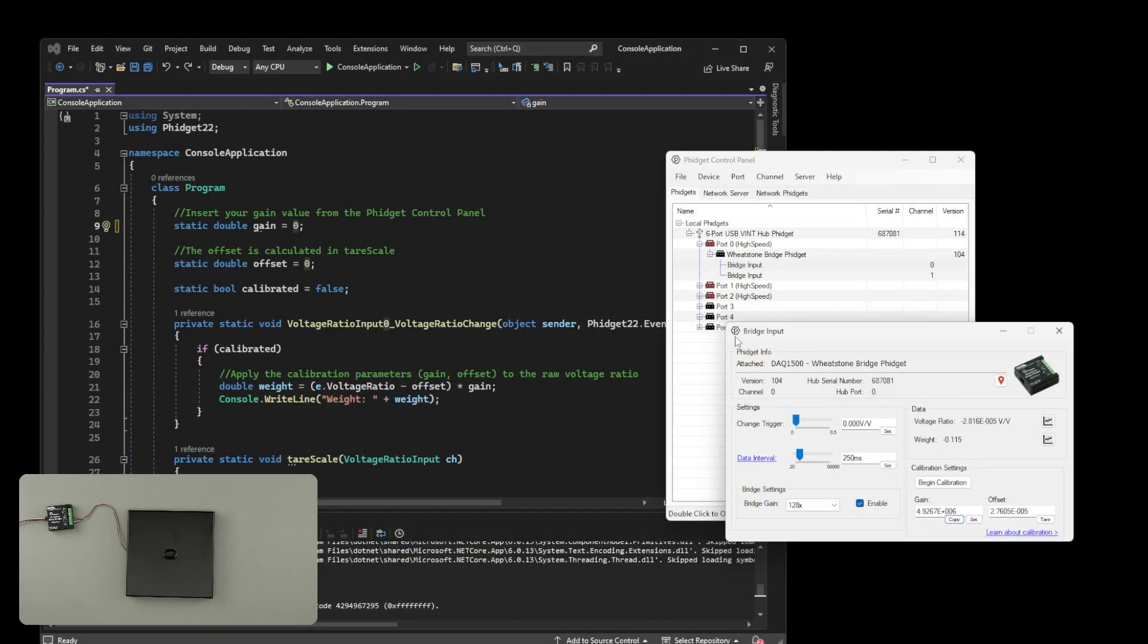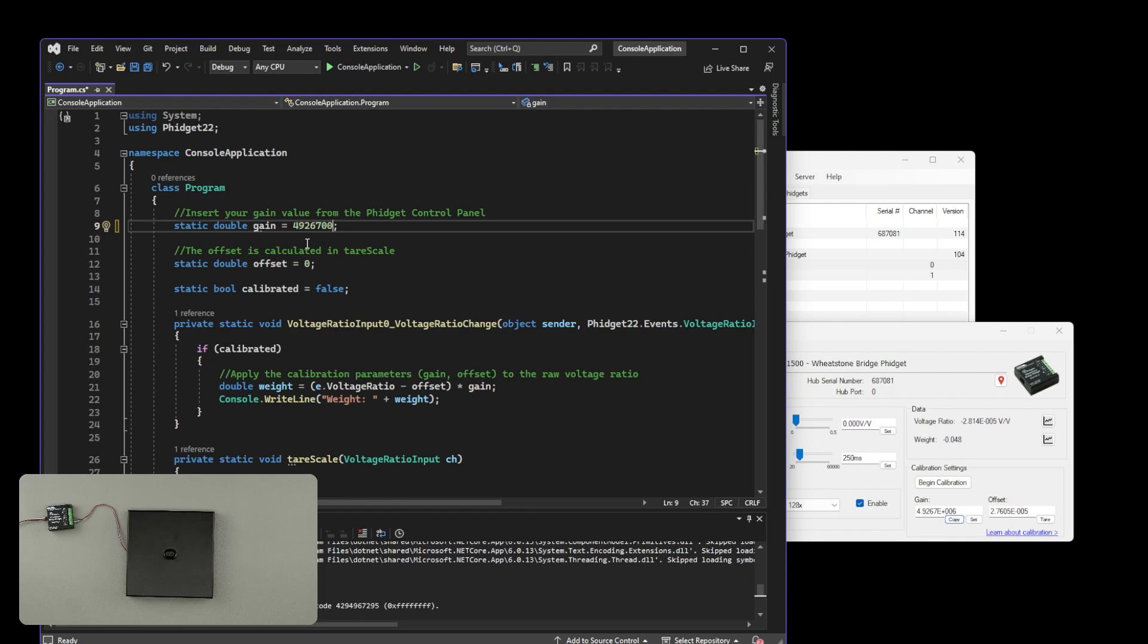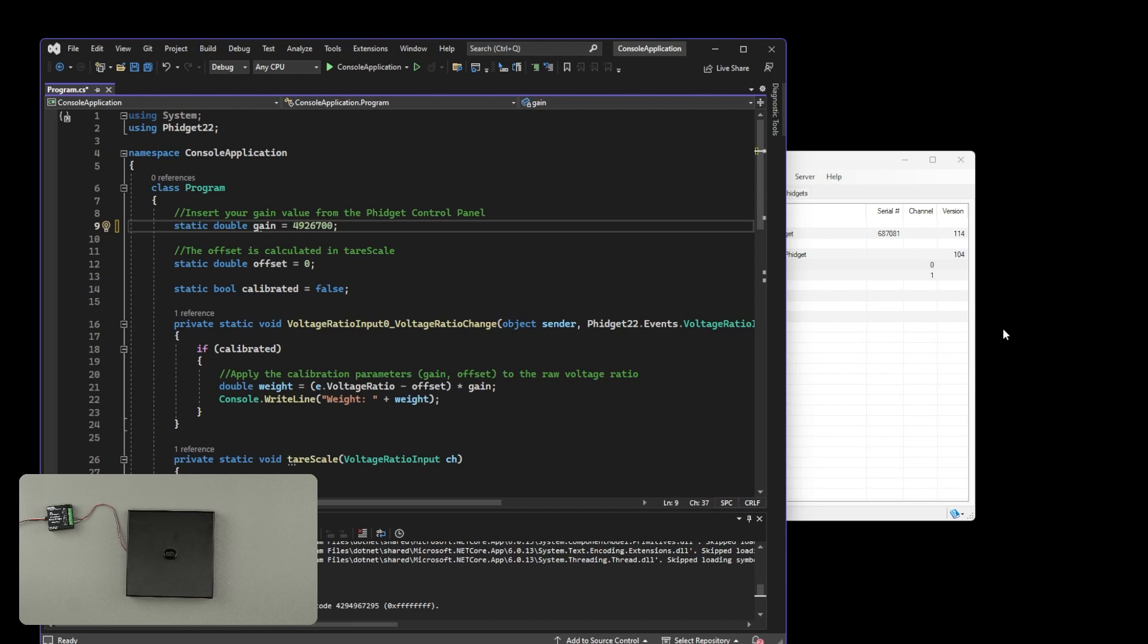Here's an example program that's available on our website in multiple programming languages. We can copy the gain from the control panel example into our program. To get the most accurate results, we recommend recalculating your offset in your software as often as your application allows. This is beneficial because things like temperature change can have a significant impact on your offset. In this program, for example, the offset is recalculated every time it's run. We can now close the control panel example and run our program.